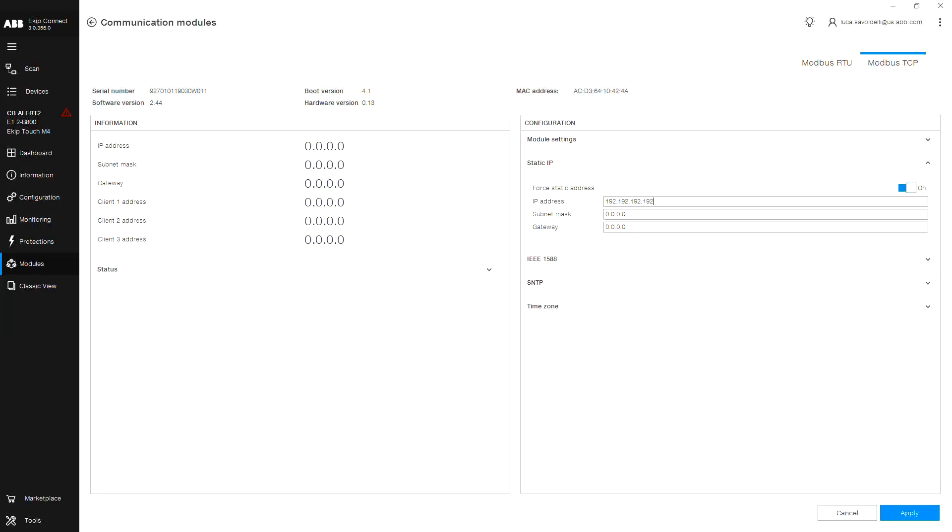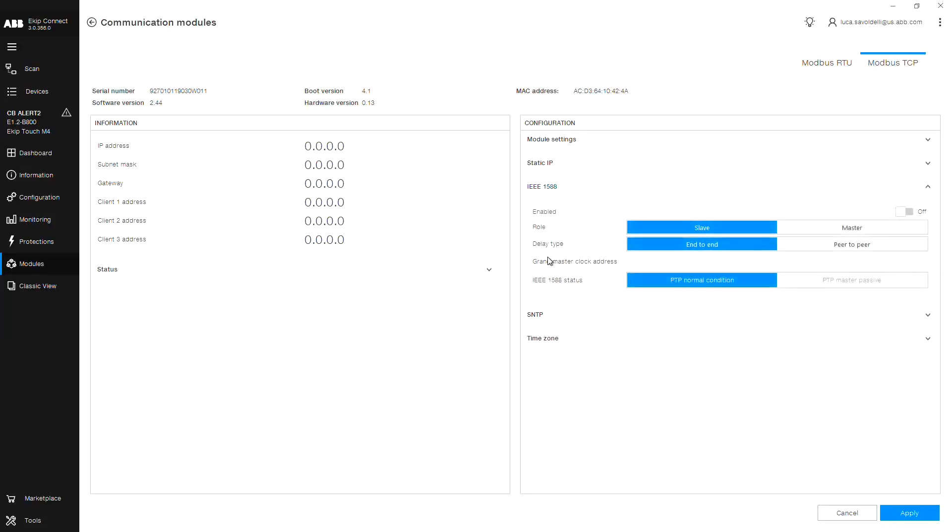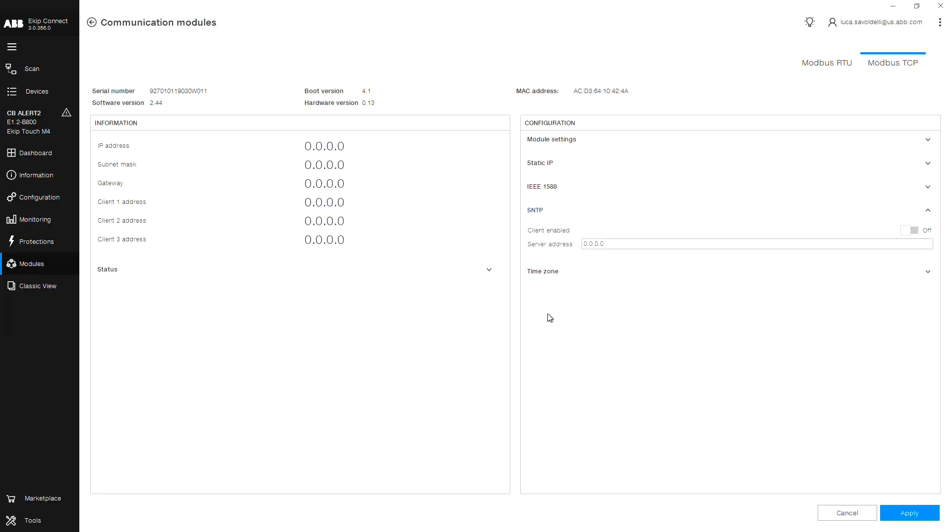The next selection is for the IEEE 1588 time synchronization function, which allows you to enable synchronization of your device up to the microsecond. In addition, we have the alternative SNTP time synchronization function, which is up to the millisecond.